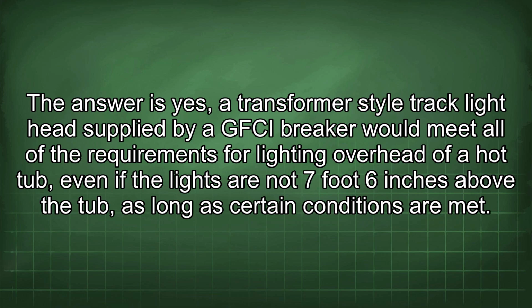The answer is yes. A transformer-style track light head supplied by a GFCI breaker would meet all of the requirements for lighting overhead of a hot tub, even if the lights are not 7 foot 6 inches above the tub, as long as certain conditions are met.